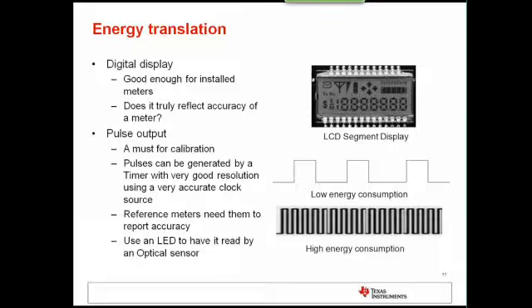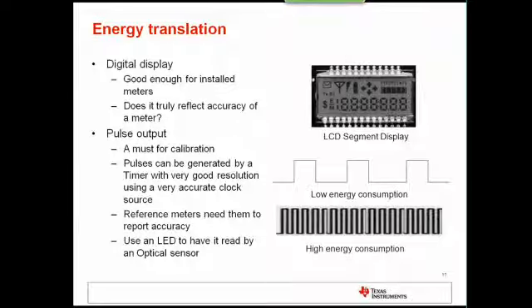So there are two ways in which energy is translated. The first way is by using a digital display, which is good enough for installed meters. However, it does not truly reflect the accuracy of the meter because there are only so many digits that you can display. There's also the pulse output. This is what's actually used to determine the meter error and is used for calibration. Basically you have pulses that are outputted at a rate proportional to the amount of energy consumed. So if you have high energy consumption, you have more pulses in a given amount of time than when you have a low energy consumption. And one option is to actually have an LED on the pulse pin so that instead of having to physically connect to the meter, you can just use an optical sensor to sense the pulses as necessary.